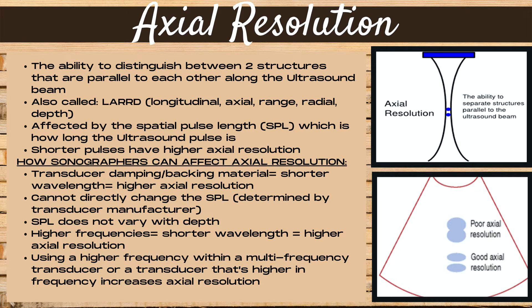Axial resolution is affected by the spatial pulse length, or SPL, which is how long the ultrasound pulses. Shorter pulses have higher axial resolution. The sonographer cannot directly change the SPL — this is determined by the transducer manufacturer. Transducer damping or backing material creates shorter wavelengths, which results in higher axial resolution. The SPL does not vary with depth on the image.